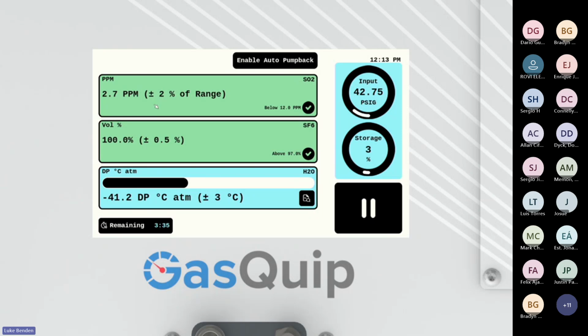So as the tests are completed, you'll see down here for the SO2 module we have a below 12.0 ppm. That is a user set test limit, and we have a defaulted value in there for each sensor module. So for SO2, there's a threshold for anything above 12 ppm SO2, and it'll flag it. This whole module will turn red instead of green and tell you, hey, you didn't pass your tests. It could be a utility standard that you have for, say, purity; on this one we have it set to 97% SF6. That could be customized to whatever you need to work off of, depending on where you're at and what you're testing. But it's just another way for the technicians to understand right away whether we passed the test or we didn't.